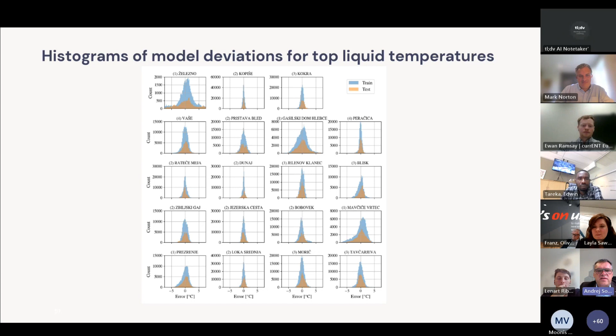Next slide, please. Andrej, just to say you have one minute left. No problem. Okay. Now the results are just presented as histograms, so you can see the deviation. The graphs are plus minus 5 degrees. Next slide, please. And this is what we can gain. This is loadability in different seasons, which we measured during the project. You can see that we can utilize the transformers almost up to 2 times per unit relative to the nominal rating.